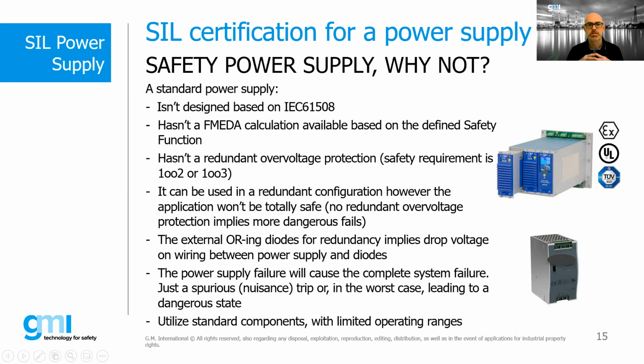So, why is it correct to use a safety power supply system? Below in the slide, we have the main reasons that lead us to advise against the use of a simple standard power supply. A standard power supply is not designed based on the directives of IEC 61508. It does not have a defined calculation for the safety function to be obtained. It does not allow redundant protection from overvoltage issues, while in a safety power supply system, redundant protections are a fundamental requirement.